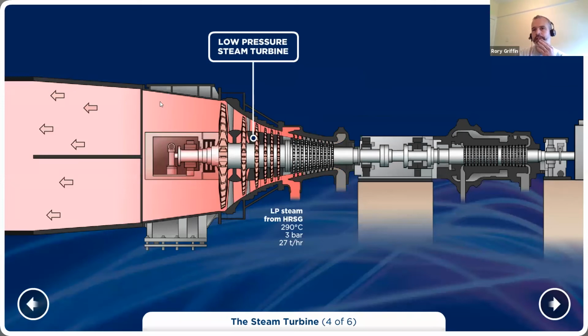Two things to note here actually in the exhaust. One is this is operated under vacuum. This helps pull the steam through the machine. You don't want the steam starting to condense back to droplets because it'll damage the blades. And the second thing is this shaft, bear in mind, is spinning at 3000 RPM, and the length of the blade is about a meter here. So the tip speed on the blade will be in the supersonic range.